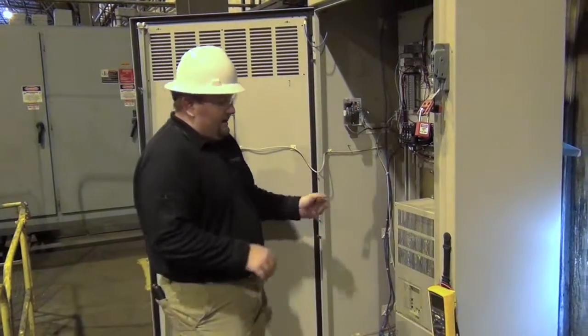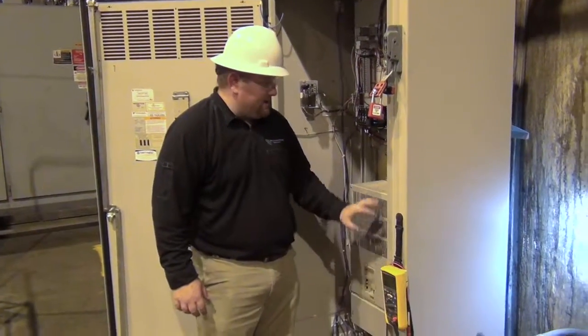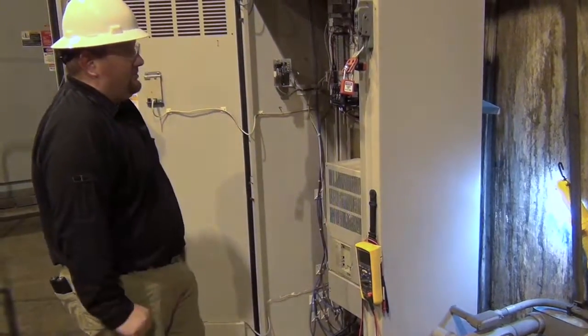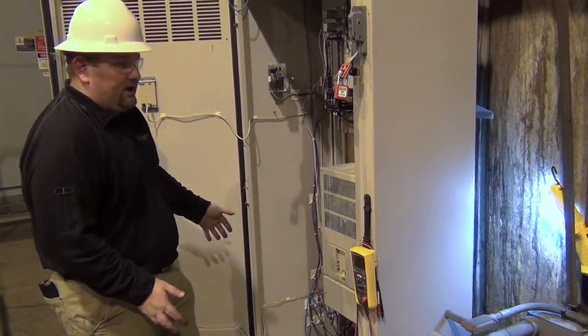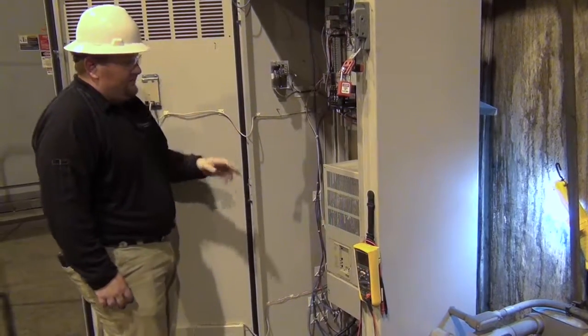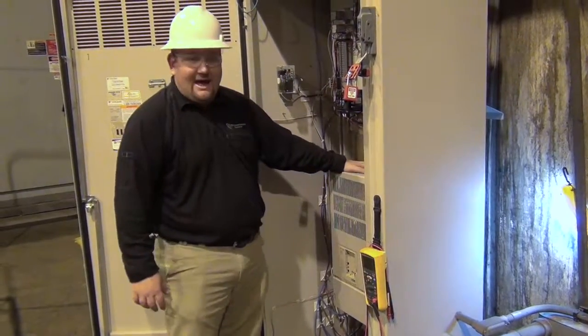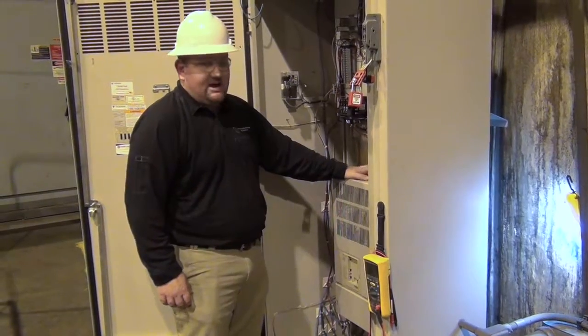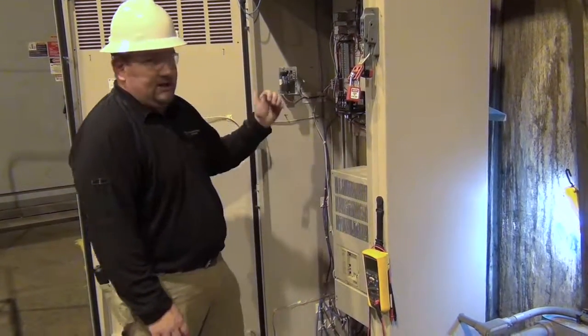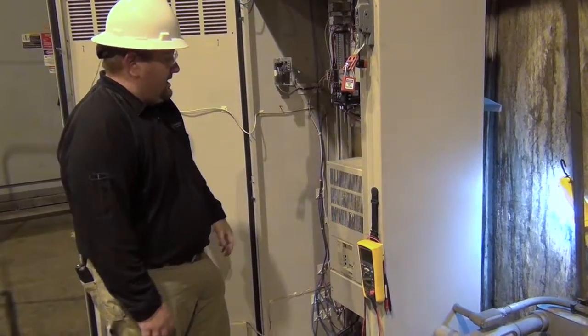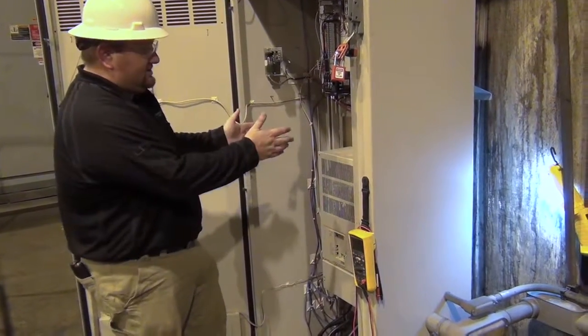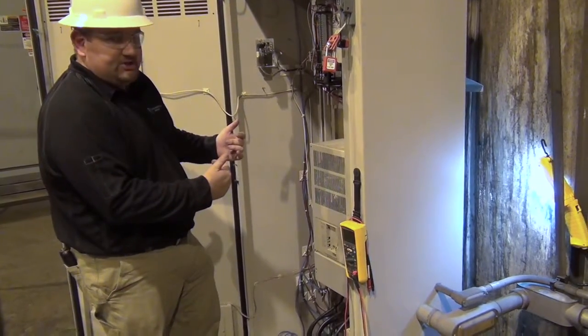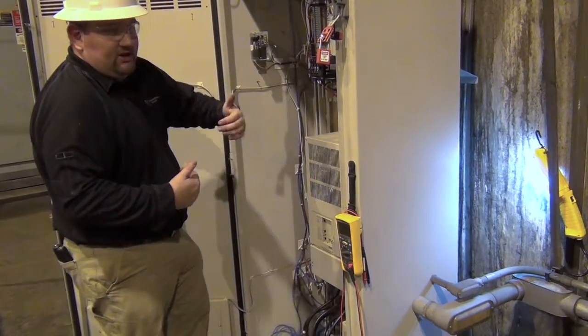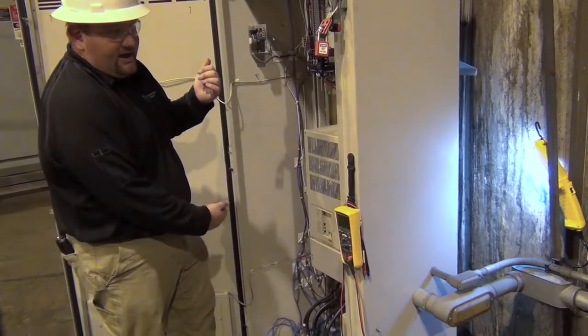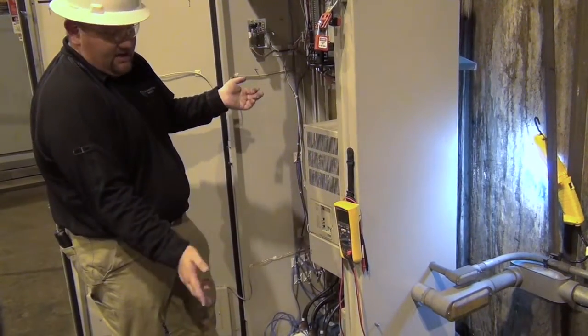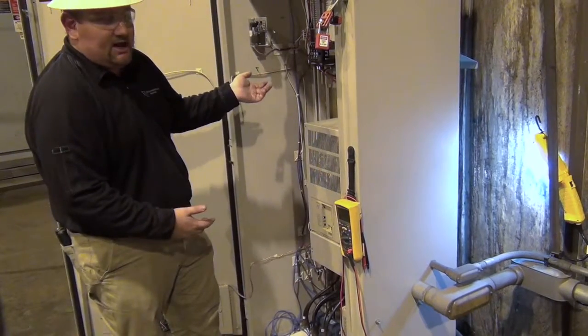So now we're back here, we have the drive all buttoned up, we've put all the covers back on. Anything, like I said, that I found that had any little bit of residual dirt, I did a quick wipe down on it. This particular drive is set up with the heatsink through the back configuration. So that allows the drive to split the heat load between the cabinet and the external ambient area. If the drive is a standard cabinet mount, you have to perform this procedure from the inside. And if you're doing it within a cabinet, the best practice is to take air from the bottom, blow up the heatsink, and then have a vacuum at the top to capture any dust.